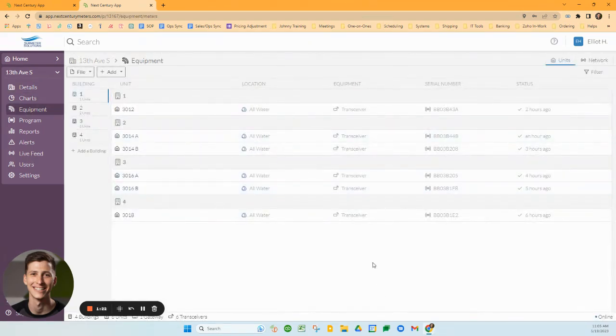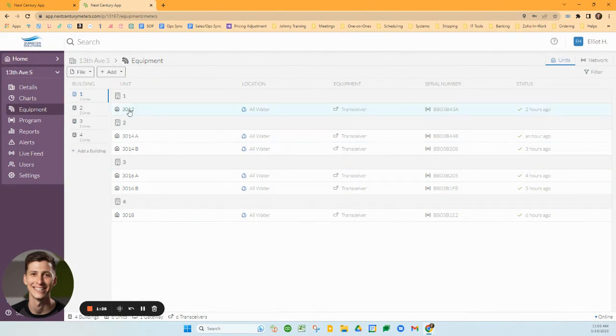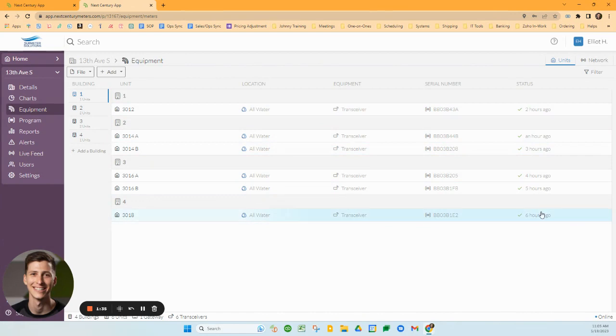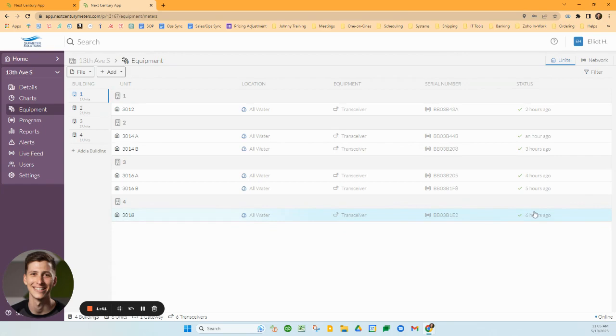The next tab is the Equipment tab. This gives specific information about each unit: what it's measuring, what kind of equipment it is, the serial number, and whether it's connected recently. These transmitters are supposed to connect once every six hours and should have a green check mark as long as they've checked in within the last 24 hours.